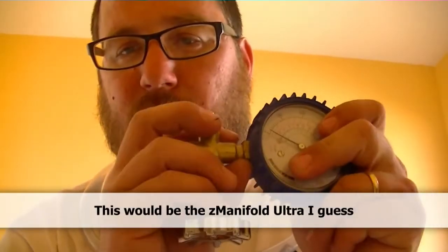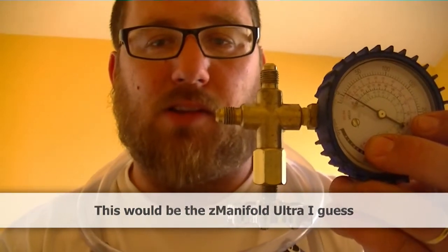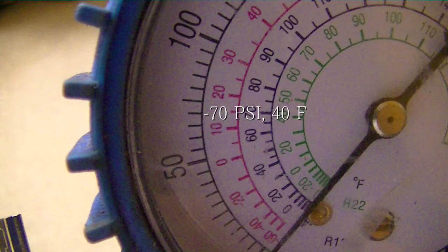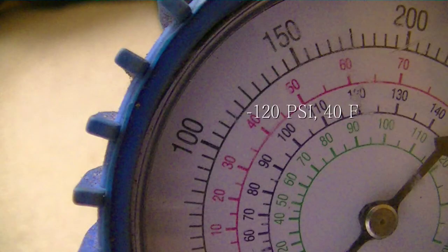I had some questions about R22 pressures compared to R410A pressures. You can go to your gauges - I have my Z manifold here, or an alternate Z manifold. My actual Z manifold has a female fitting I put on, but this is what I used when I did refrigeration stuff, though not very often. If you had a 70-pound suction pressure, you look on your gauge and track down what temperature that is. For R22, let's say that's about 40 degrees. Now if you wanted to find 40 degrees on R410A, you'd look up there and see it's 120 - you can see that right here on the gauges. So you can get a rough idea of what your suction pressure would be on R410A. Of course that may not be the best method for translating your pressures, but it'll give you an idea of what it might run.